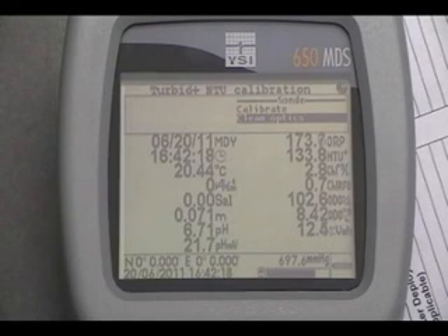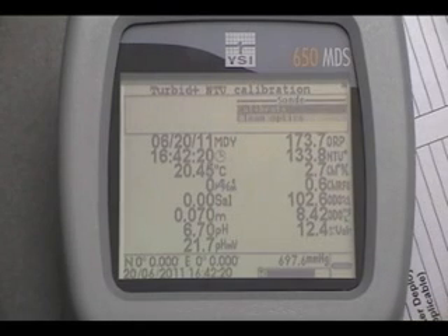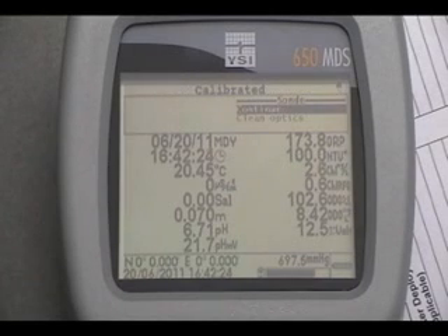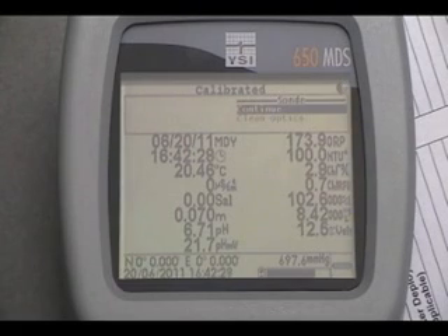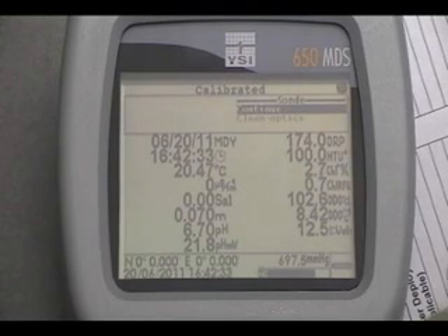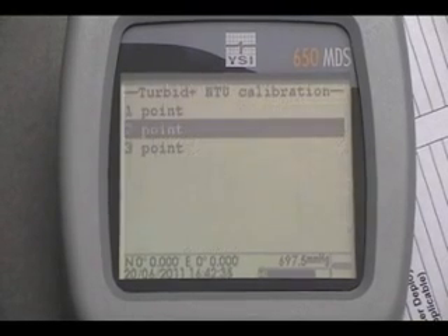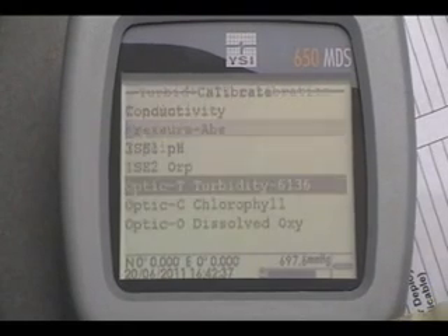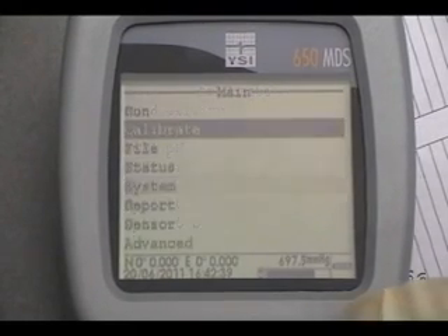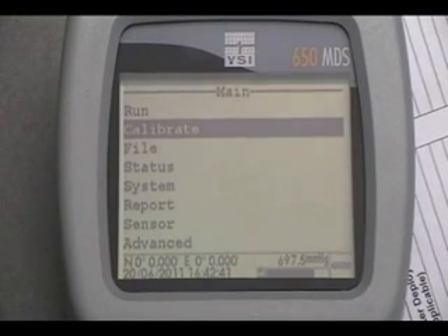Step 18. Highlight Calibrate and press Enter to confirm the second calibration. Record the post-calibration value for 100 NTU on the calibration worksheet. Press Enter to continue, and Escape to return to the main menu. Step 19. Empty the cup and rinse sensors and cup with deionized water. Turbidity is now calibrated.